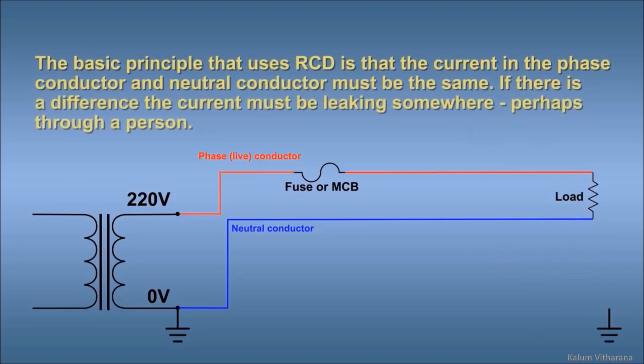The basic principle that an RCD uses is that the current in the phase conductor and neutral conductor must be the same. If there is a difference, the current must be leaking somewhere, perhaps through a person.